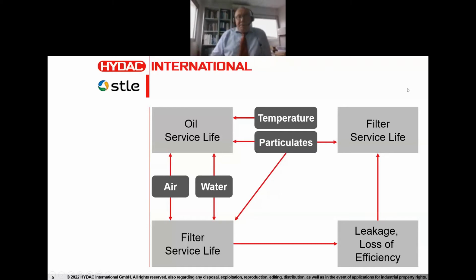which is what affects the oil service life. Well, obviously temperature, particulates, but not all kinds of particulates. For example, silica sand, in terms of chemical activity, is really innocuous. However, it does lead to abrasion, and in that case, it generates metallic particulate with very highly active surfaces. In which case, it can lead to a chemical impact on the oil service life. And then we have truly chemical contaminants, which would be air and water. Air by virtue of adiabatic compression, microdieseling, which leads to very, very highly elevated hotspots, temperature hotspots.